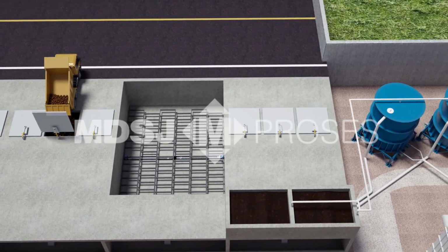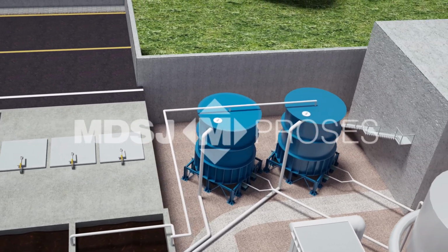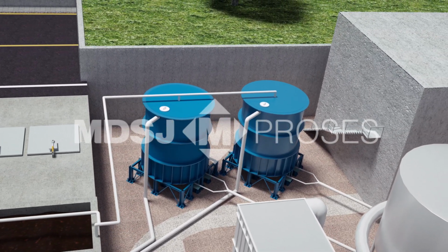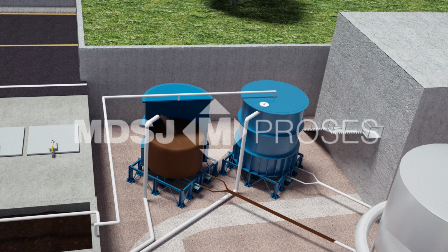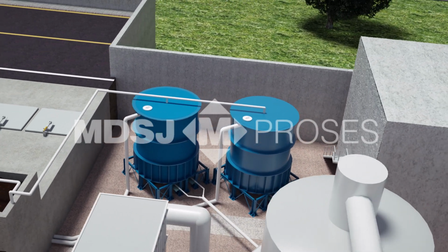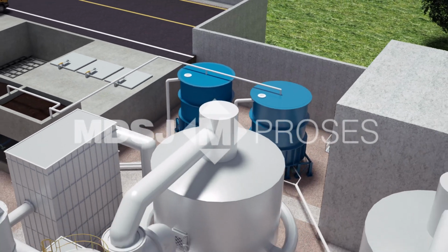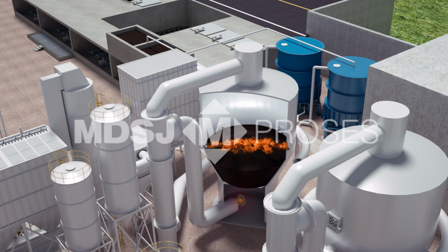22 to 26% dry, dewatered sludge at decanter coming from treatment and WWTPs gets dumped into underground bunkers. Progressive cavity pumps, located below the bunkers, convey the sludge to the above-ground intermediate silos. The sludge pumped from the underground bunkers is stored in above-ground silos. The progressive cavity pumps, installed below these silos, convey the sludge to the fluidized bed incinerator.